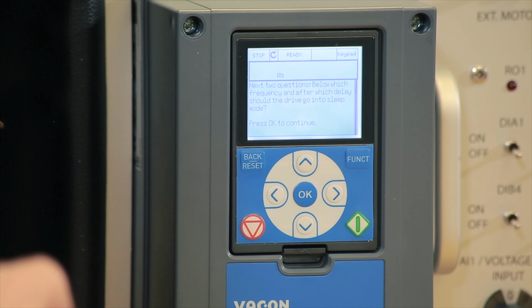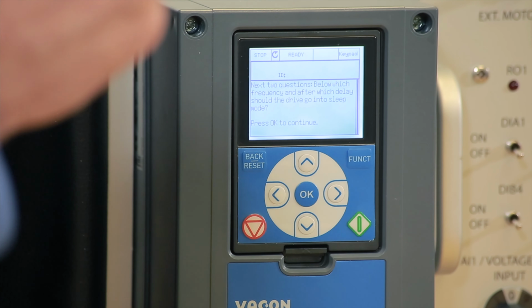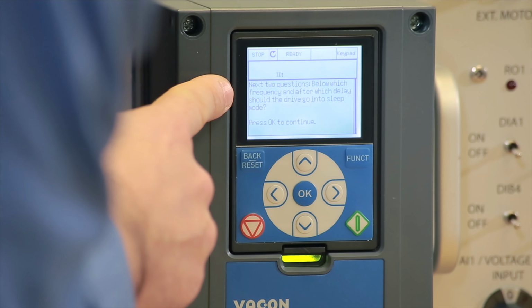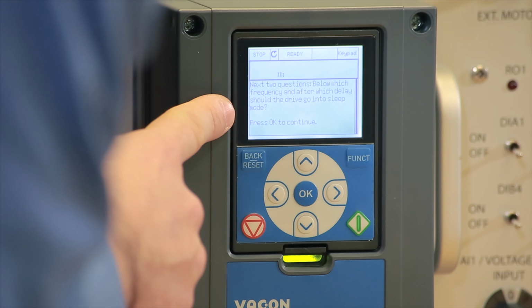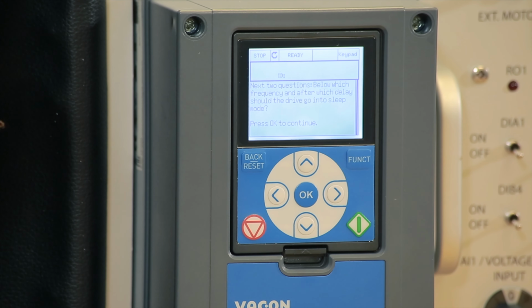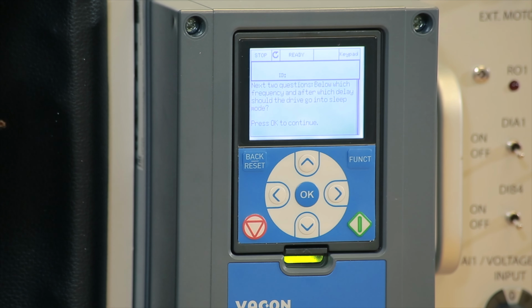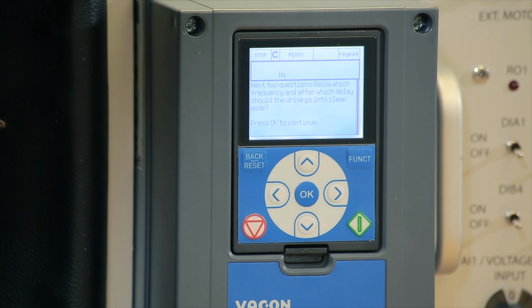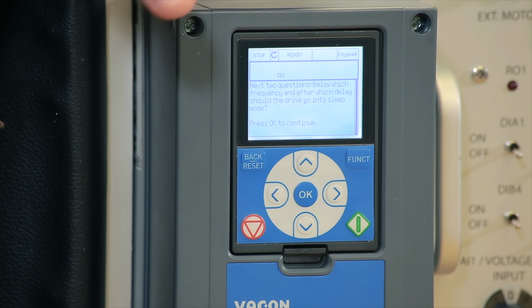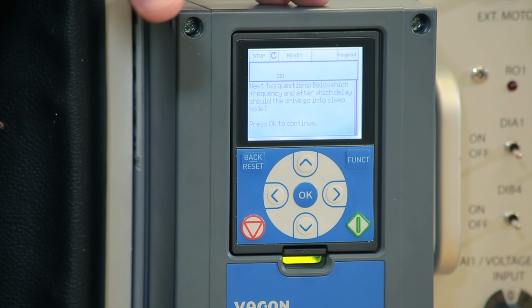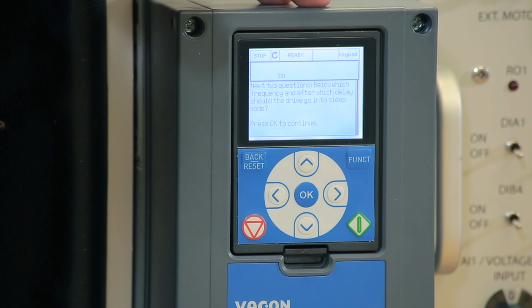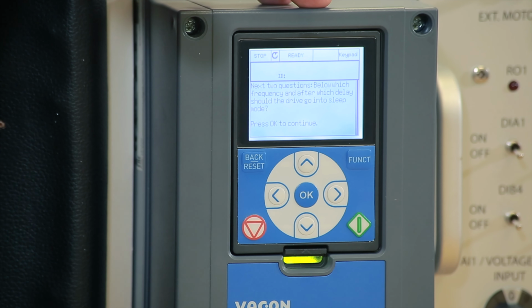So the next question will tell us the two questions the drive asks: below which frequency and after which delay should the drive go into sleep mode? So this is very important. If the drive is running at 60 Hertz at full speed and we want to put it in sleep because we have already achieved our set point, we want to start decreasing the speed. And the drive has a timer that we'll program shortly that says, after we start slowing down the speed, after which frequency do we want to use the internal timer in order to put the drive to sleep. And we'll see that.